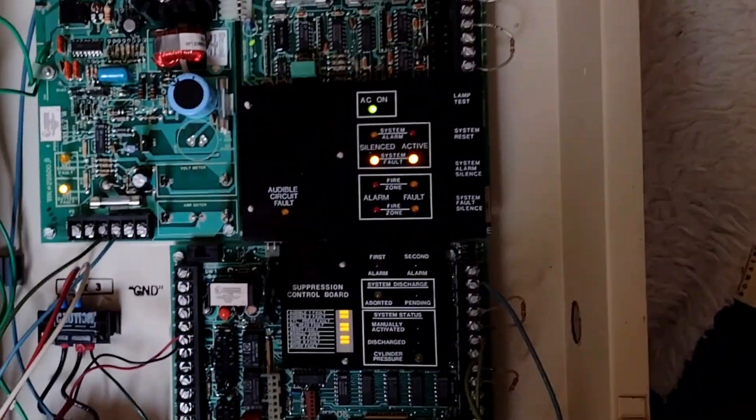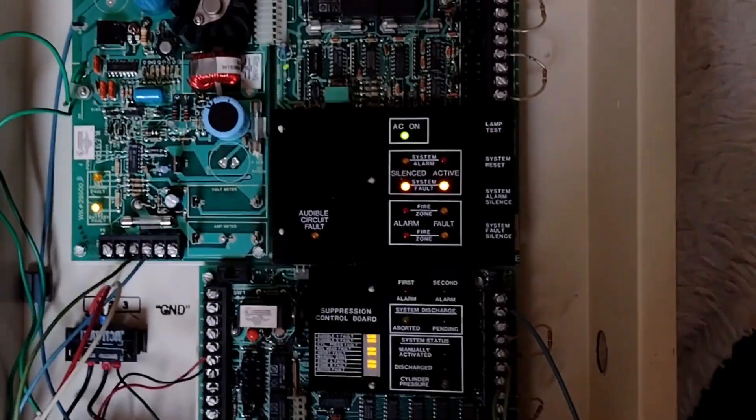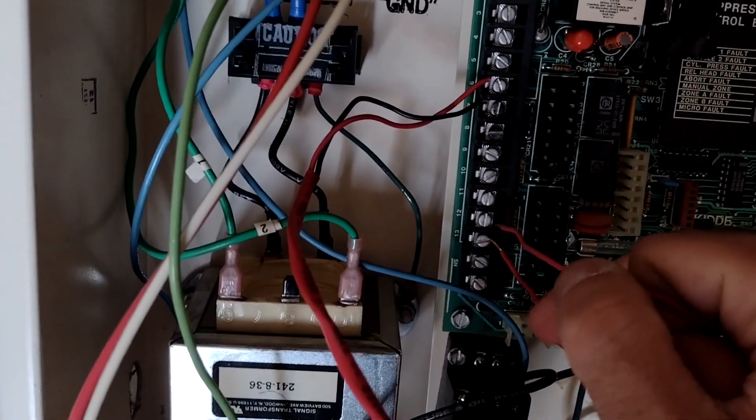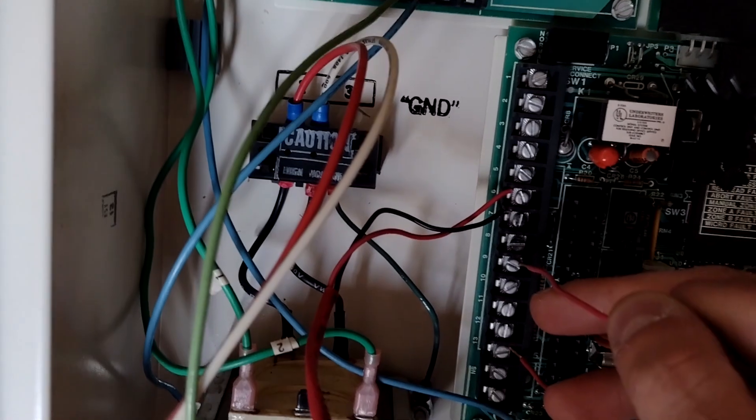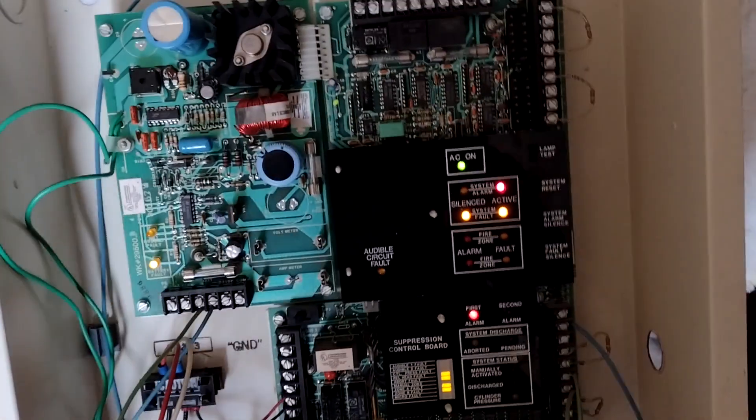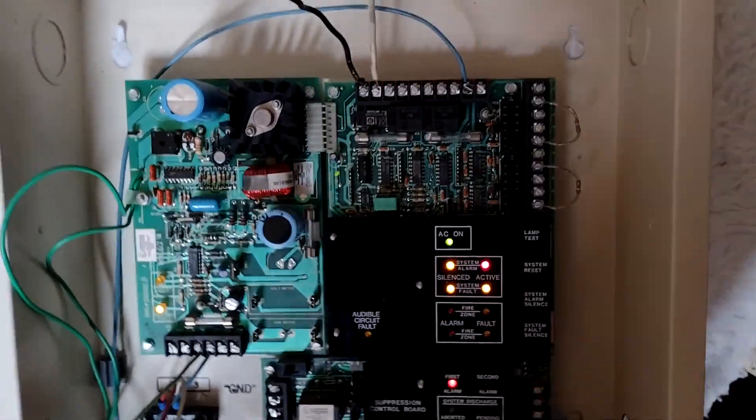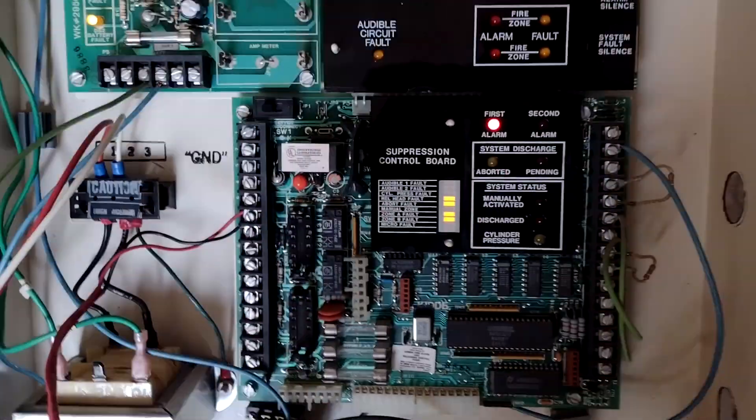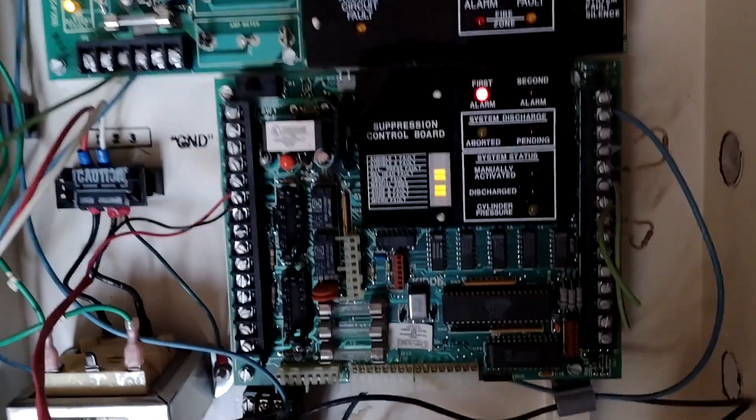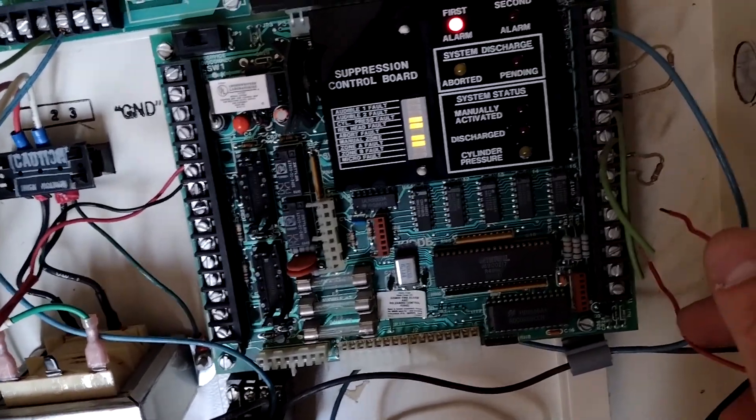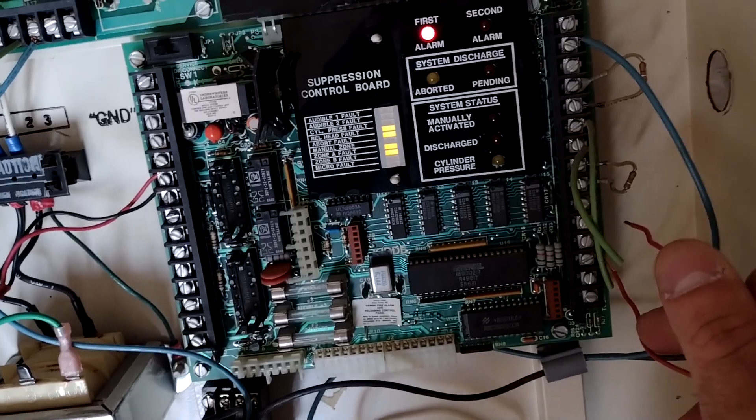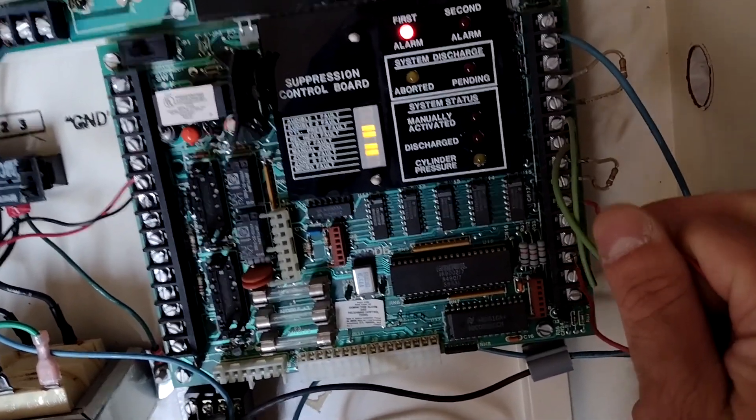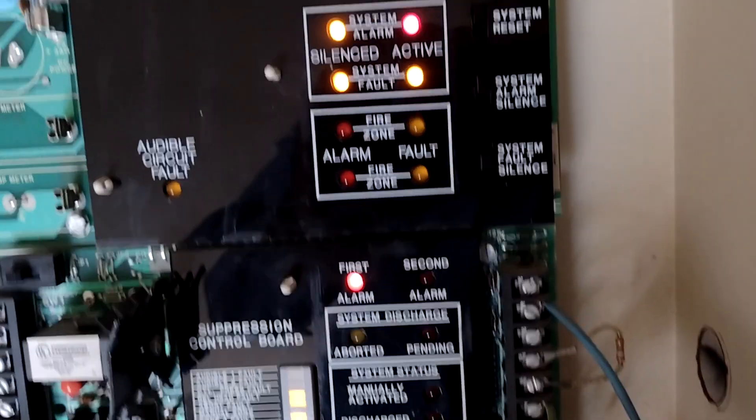Now we're going to run through the worst case scenario. Let's say the fire started above the floor. We're going to activate zone one on the suppression control. And I'm just going to silence that so I can keep talking. Now the fire's gotten a little bigger, and it actually melted through one of the tiles, one of the floor tiles, and it's now spread to under the floor. So now we're going to short the second zone with the first zone still on alarm.